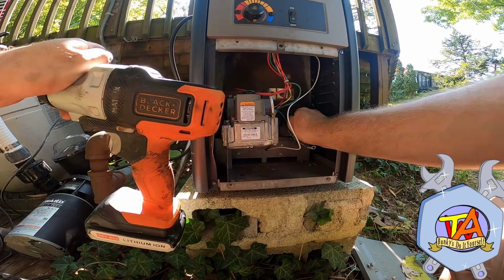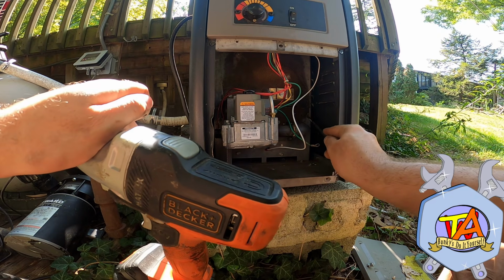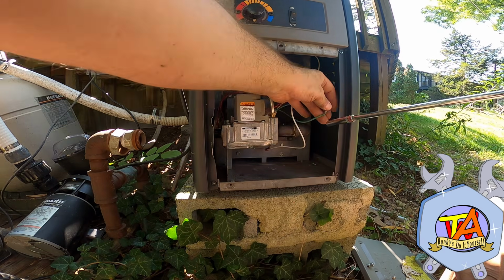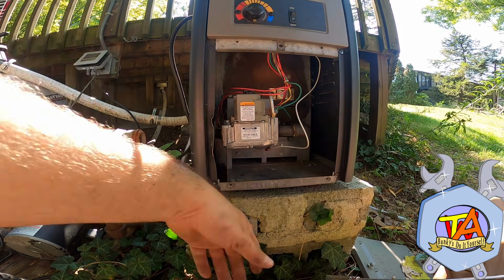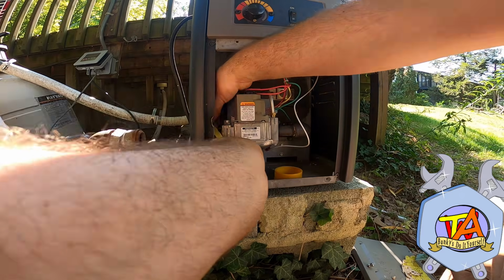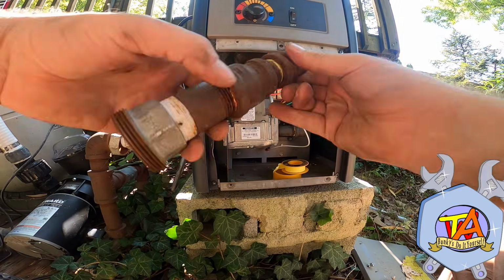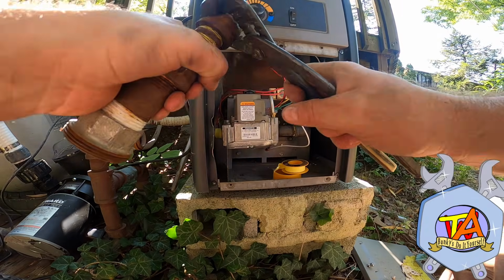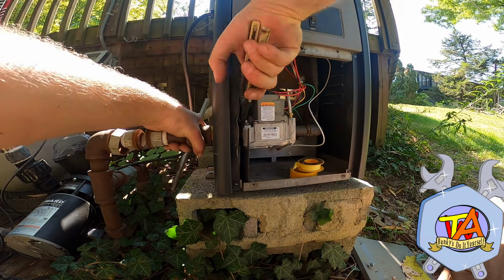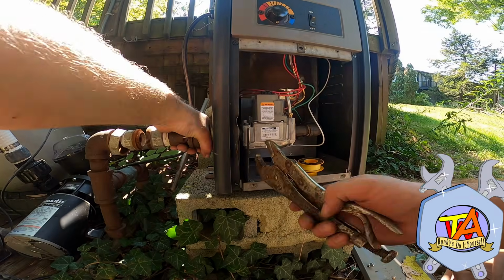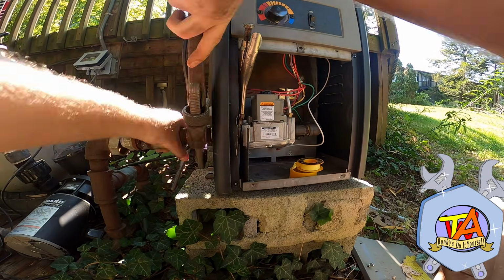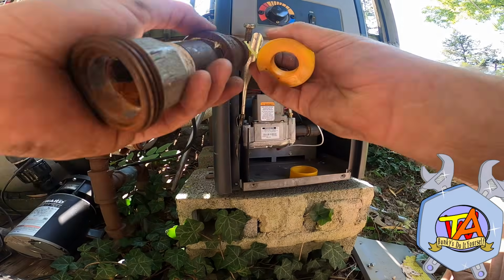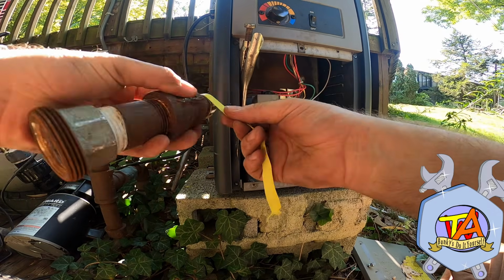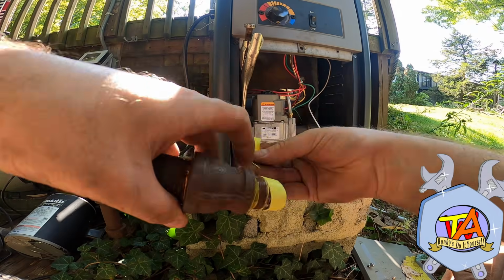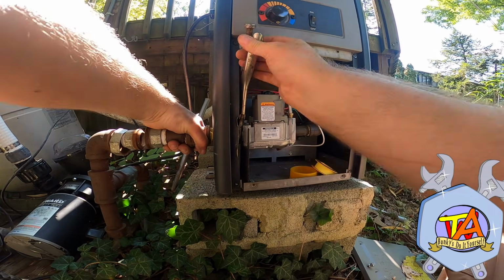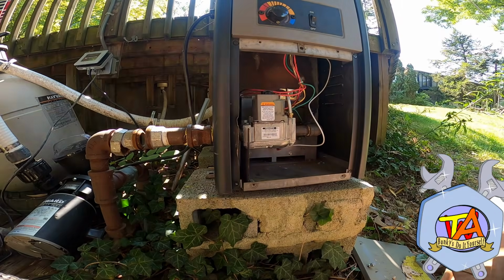And here I am scraping some of the rust with a screwdriver in order to get a better ground. And I used the yellow pipe thread sealant tape in order to seal the gas pipes that were damaged while this repair was going on. I don't know why, but every time I put on any type of pipe thread tape, I always end up getting very dyslexic and having to redo it. And now I can reconnect the union.